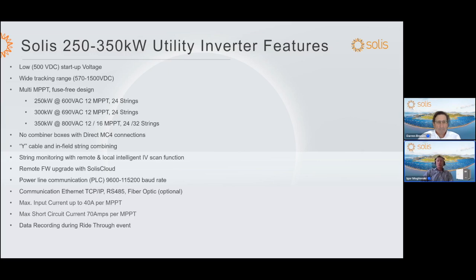It has a feature of data recording during a ride-through event. In the event of a ride-through, we record the event, and that data can be retrieved over Modbus communication. It has integrated anti-PID and PID recovery. Anti-PID is during daytime, PID recovery is nighttime recovery. Both are available, but one needs to be selected at a time. Power response time is less than 60 milliseconds to a power command for reactive and active power support. Night-time support, so you could have reactive power support at night. It is designed in a NEMA 4X C5 enclosure, so it can be installed in the most harsh environments, by the sea or any other harsh location.